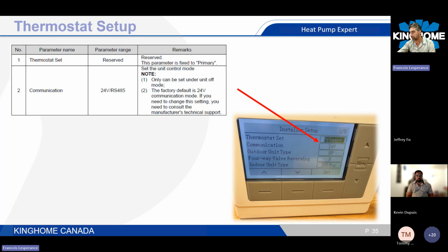All the rest of the installer setup in the menu is accessible via the white thermostat or the touchscreen. You can do it both ways. You can program from the white thermostat directly from the mechanical room, or you can go upstairs, talk with your customers, and program the system right in front of them. So the two ways are good to go.